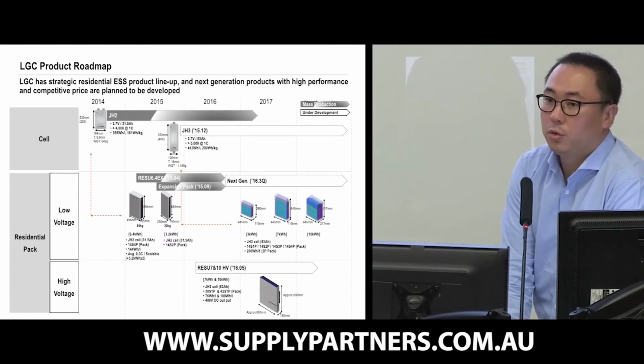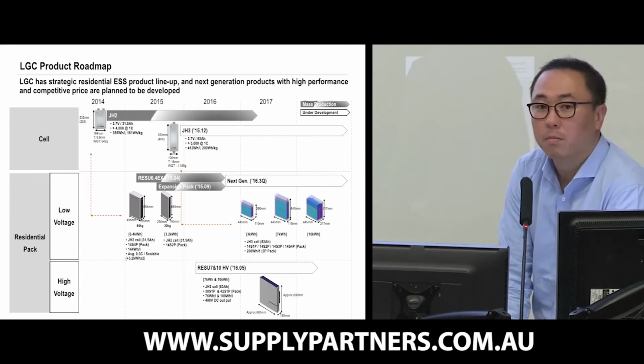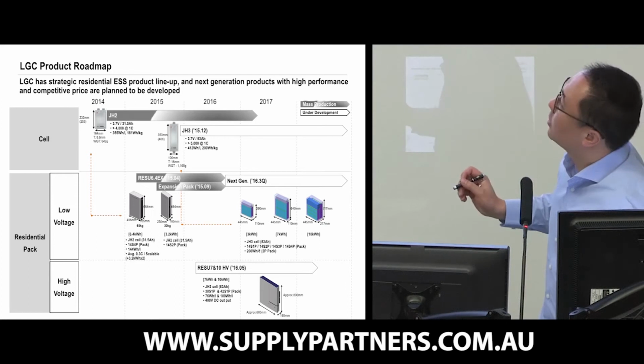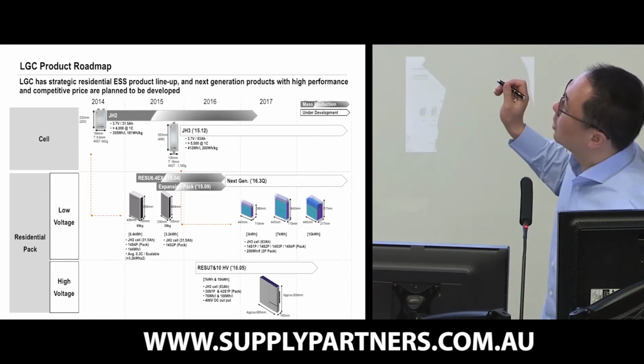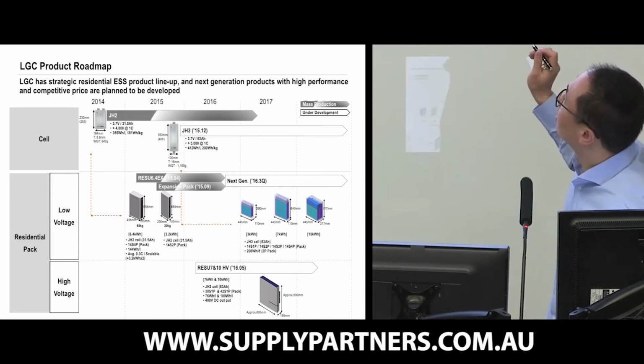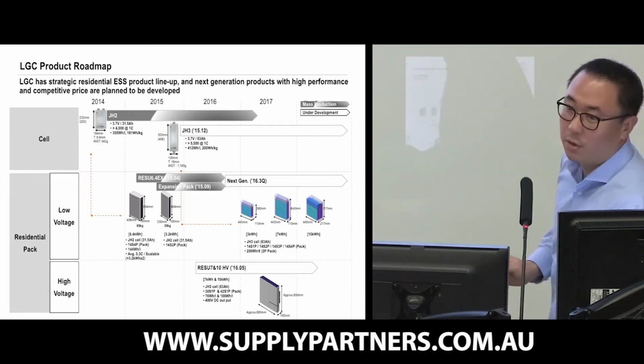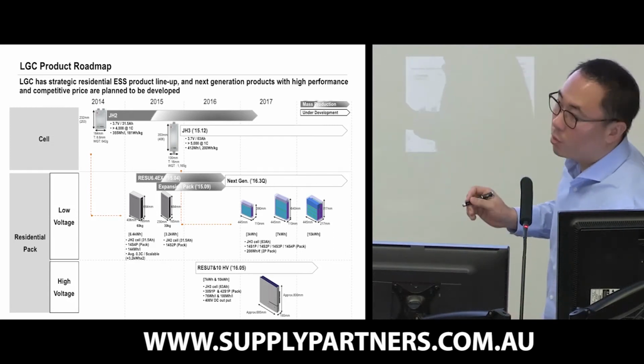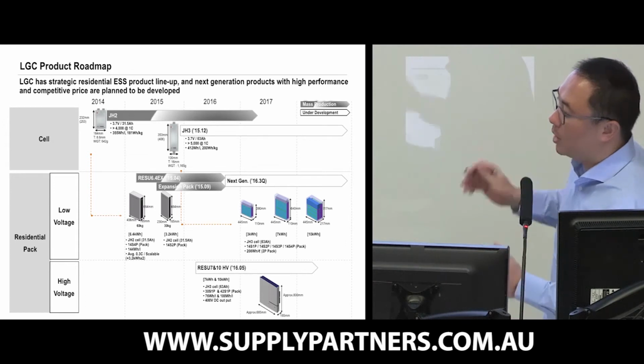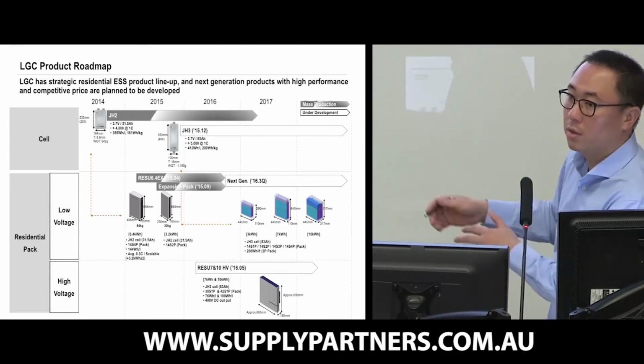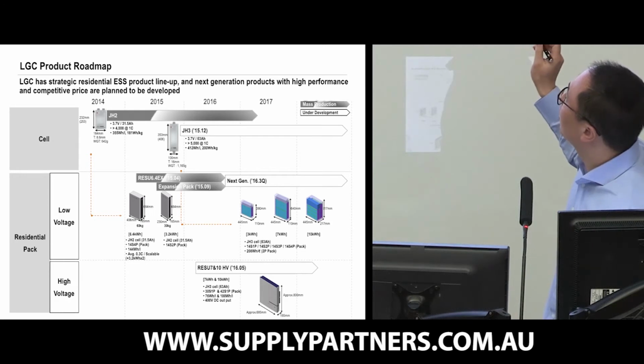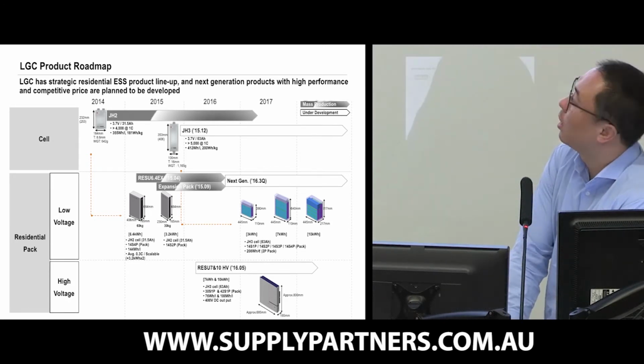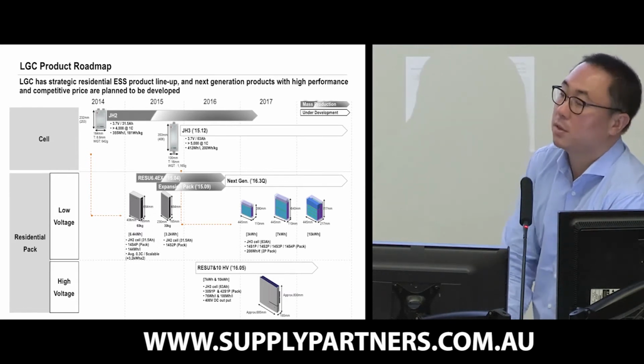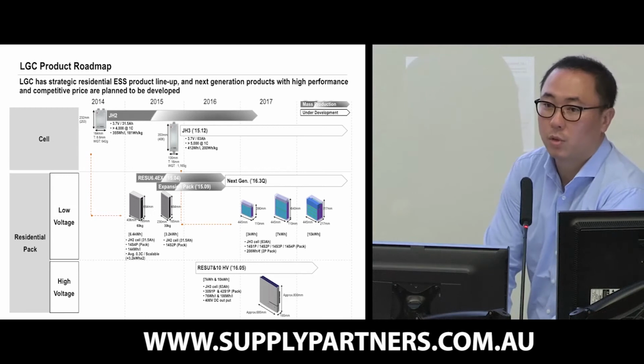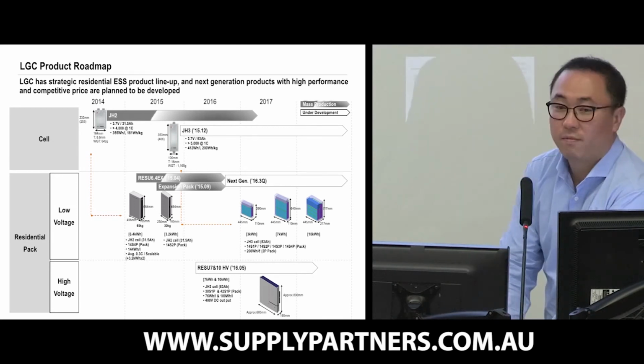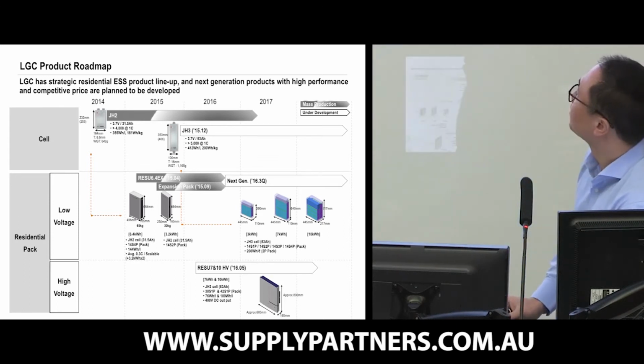We are also launching a new product after mid next year. The current product is scalable with expansion units, but the next generation will have 3 different products without expansion units—instead, main units connect in parallel to increase capacity: 3, 7, and 10 kilowatt hour versions at 48 volts. The current unit is IP21 indoor rated, while the next generation will be IP54, suitable for outdoor use.